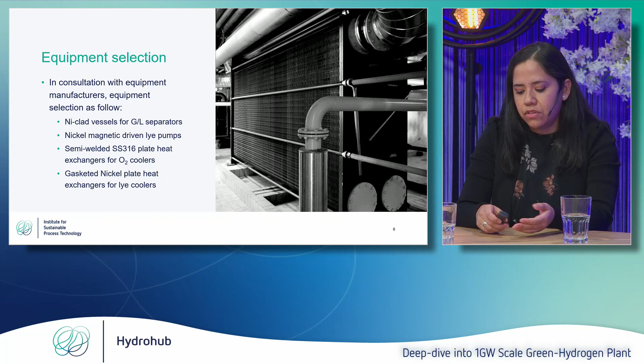We selected nickel magnetic-driven pumps for the lye pumps. For the gas coolers, for oxygen, we have semi-welded stainless steel 316 plate heat exchangers, and for the lye coolers we have gasketed nickel plate heat exchangers.